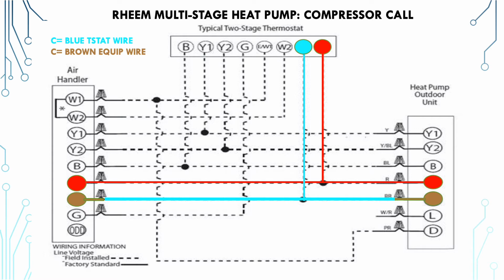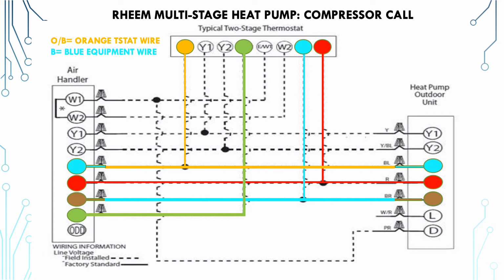You always have to pull off the panel or find the paperwork or the manual, and you need to look at the ladder diagram or the schematics for that particular unit. If they're not available, you might have to trace things around to figure it out. Now, a lot of times, especially on heat pumps, you can figure that out fairly easily by just looking at the actual defrost control board. Our green wire goes for the fan call. There's no green wire going out to the heat pump. There's no need for it.